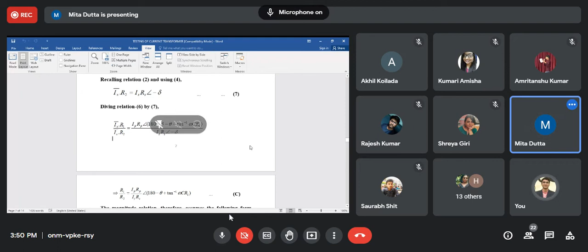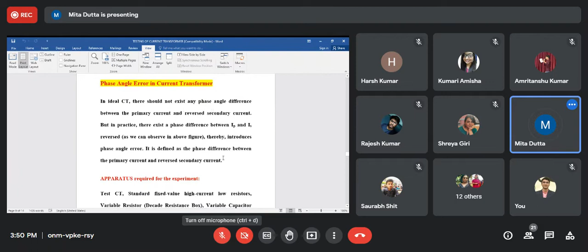Now the ratio error, it is the nominal ratio minus actual transformation ratio or current transformation ratio divided by nominal ratio into 100, and a nominal ratio I've already told you, rated primary current by rated secondary current, and that is the phase angle error. Now the apparatus required here from the same diagram what we have seen, we need, these are the R1 is the decade resistance box and C is the decade capacitance box, R2 is a fixed resistor, RP and RS, these are the low value resistor or low resistance, and that is why it is defined as 4 terminal.